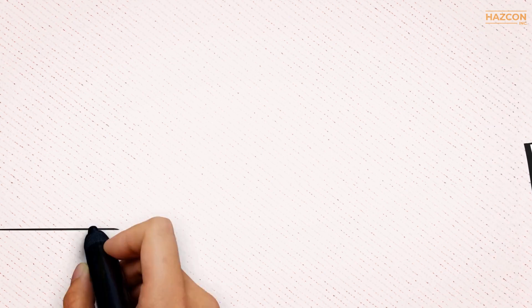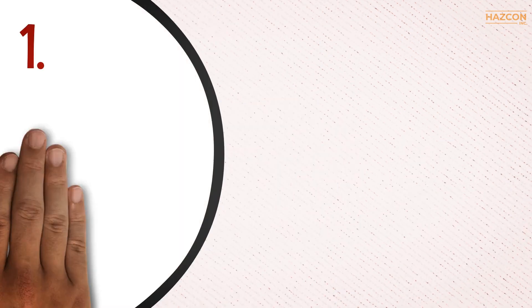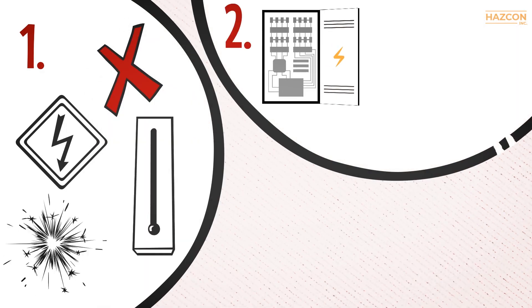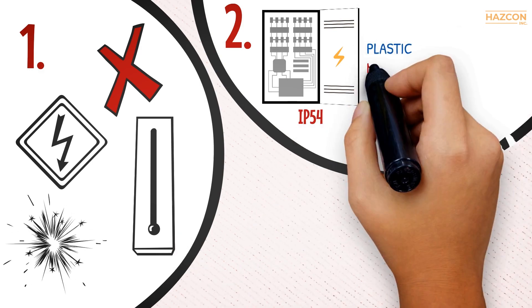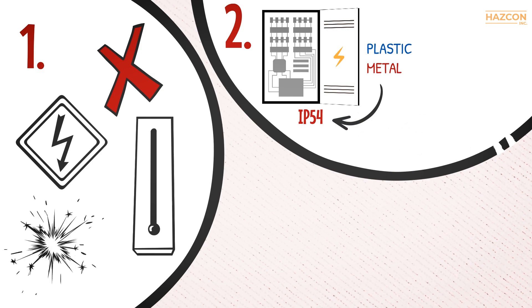The increased safety protection technique involves designing electrical devices so that arcs, sparks, and hot surfaces are avoided. The electrical components are enclosed in an IP54 rated enclosure. The enclosure can be made of plastic or metal but needs to be able to maintain the IP54 rating at the minimum.